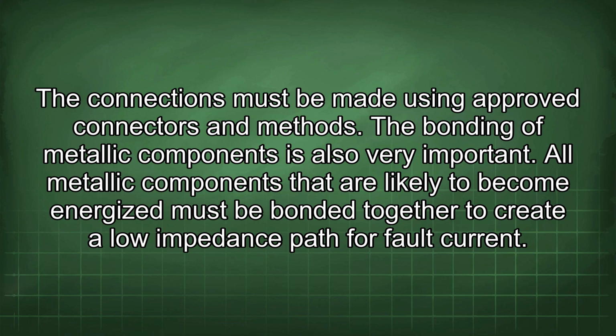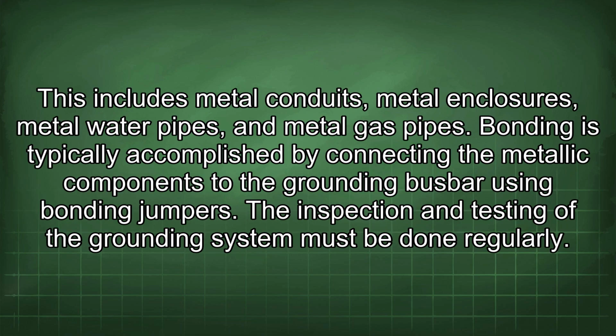The bonding of metallic components is also very important. All metallic components that are likely to become energized must be bonded together to create a low impedance path for fault current. This includes metal conduits, metal enclosures, metal water pipes, and metal gas pipes.